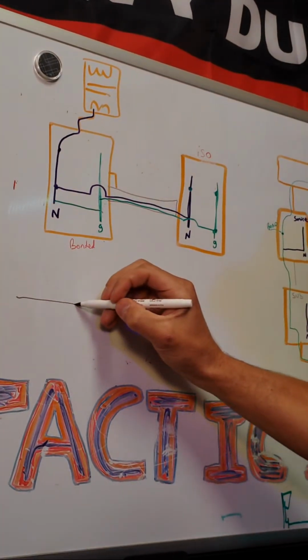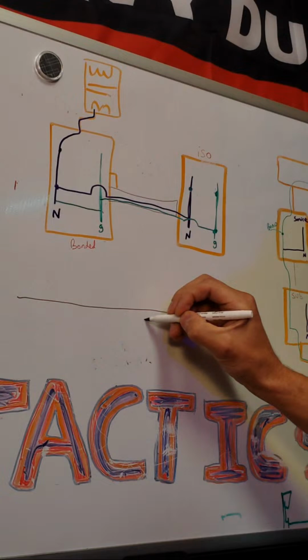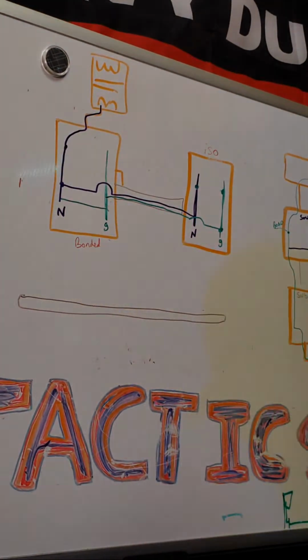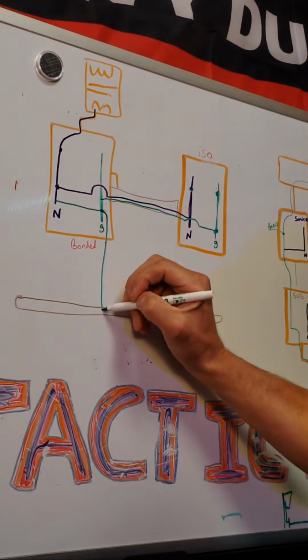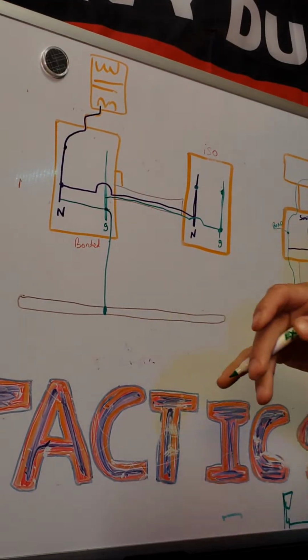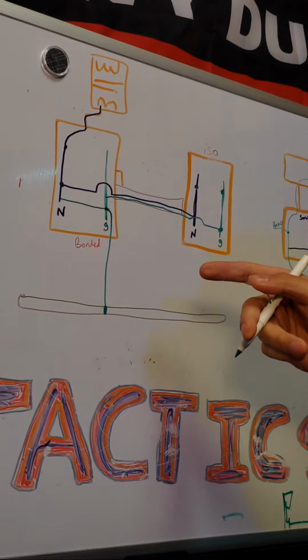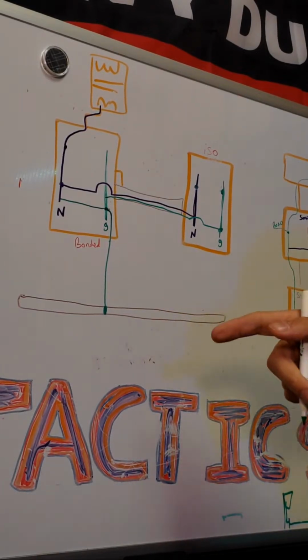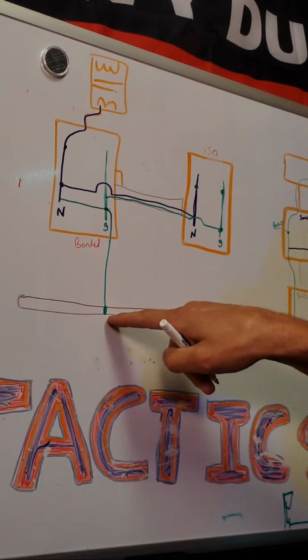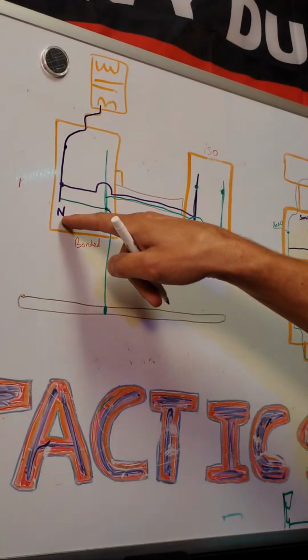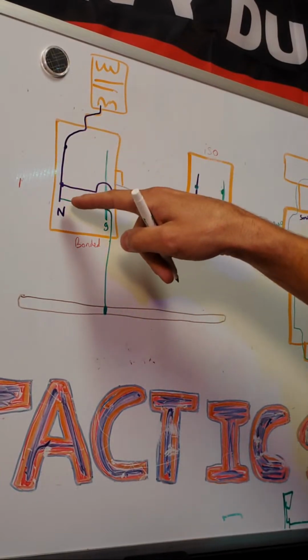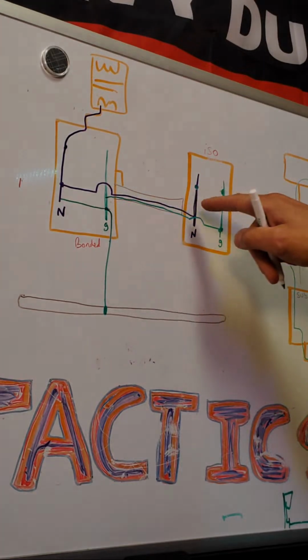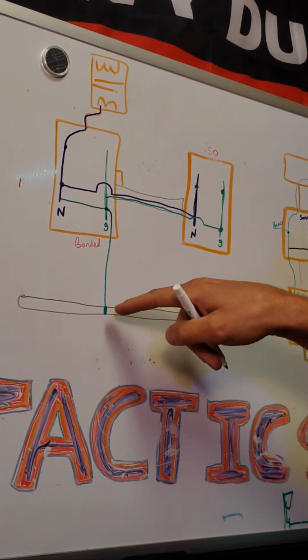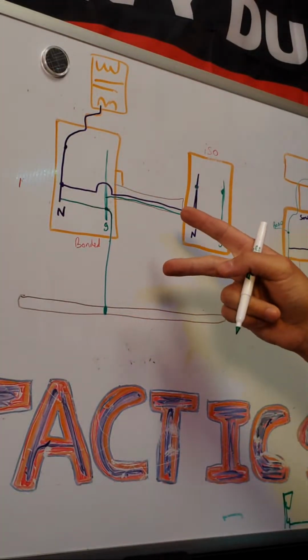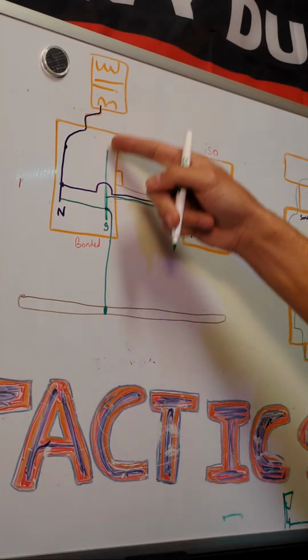If we have underground metal water pipe, copper, they're supposed to use it as an electrode. We want to bond to this to create kind of an equal playing field of what the voltage in the area is going to be on the earth. This isn't really creating our actual ground. Our actual ground was already created by the grounded conductor, which is a neutral, and the green is the grounding conductor. This grounding electrode doesn't really decide our voltage. It can help with that, but the neutral already did that because it's the source to our transformer.